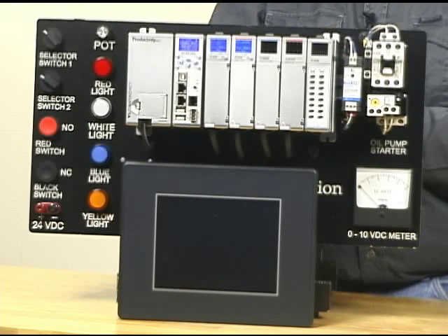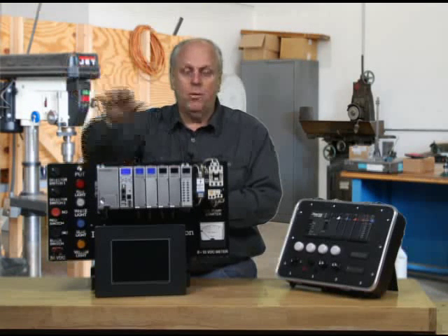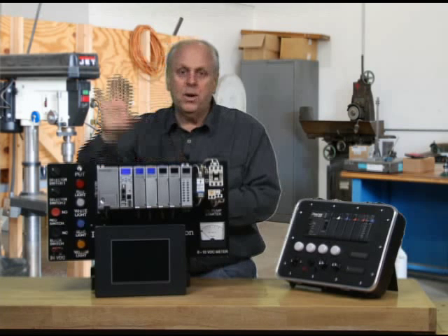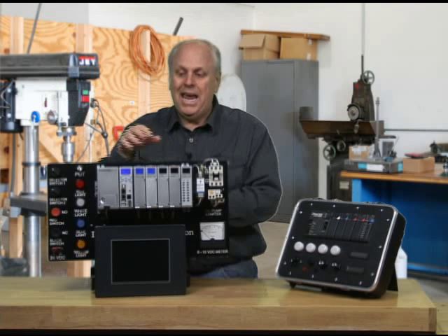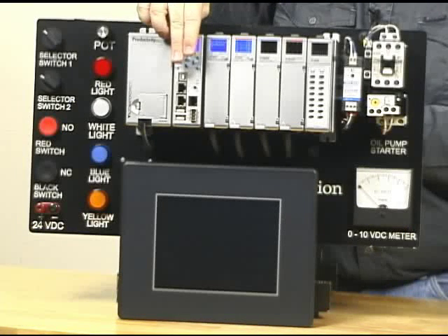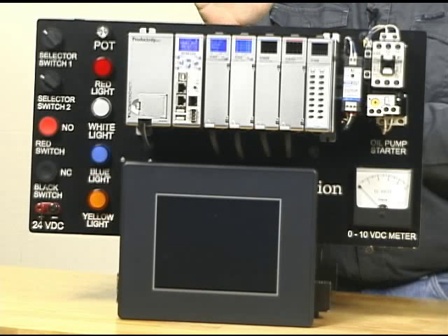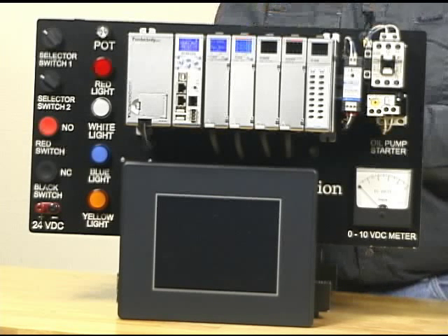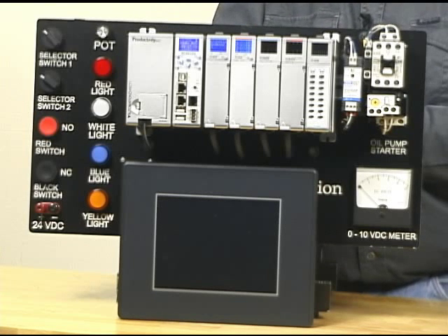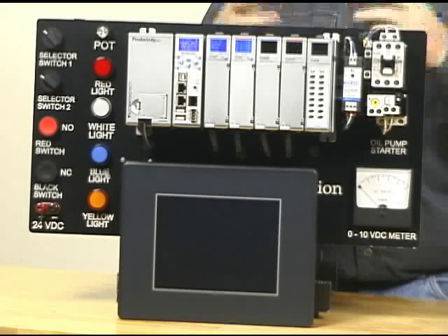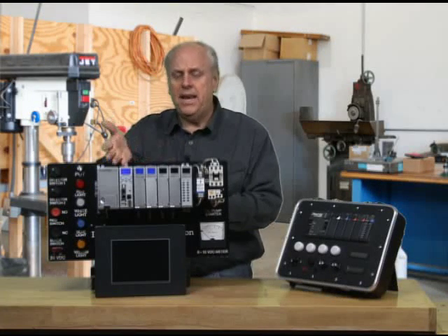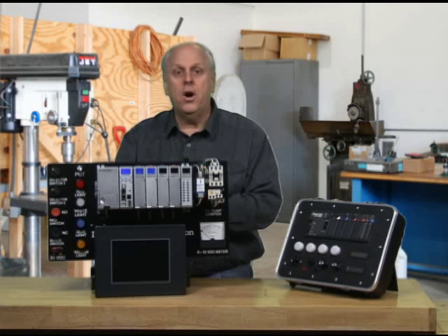On top of that, not only does the remote I/O system support remote racks, it supports frequency drives. So I can plug in frequency drives out there on the Ethernet network, and they just appear. All the settings that are in the drive appear in the CPU, so I don't have to do any kind of mapping. All I got to do is assign them names, tag names again. Another feature is I can hook this up to an SQL database or an ODBC database so that I can get data out of the PLC. So I can take the data from here and store it into a database for long-term storage.